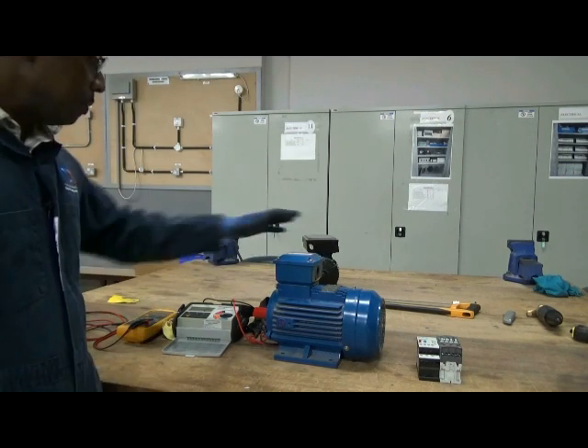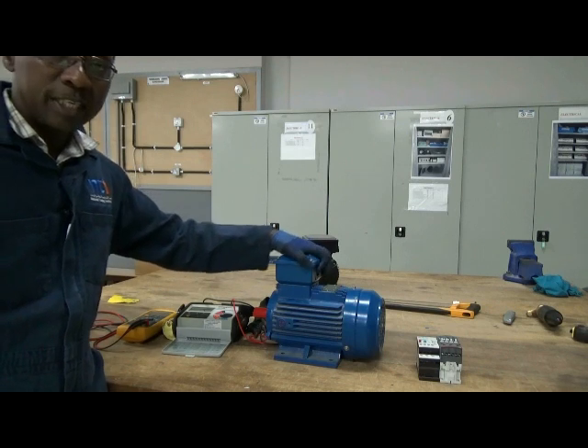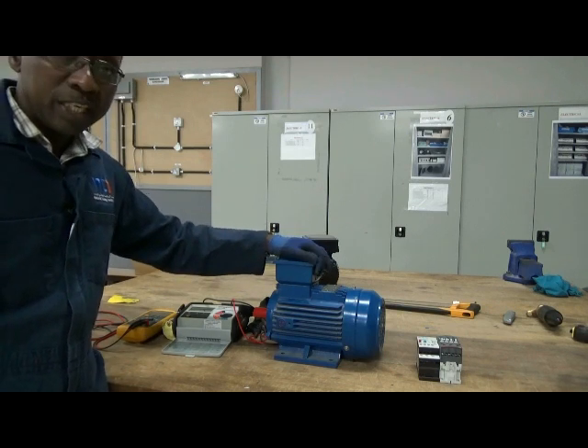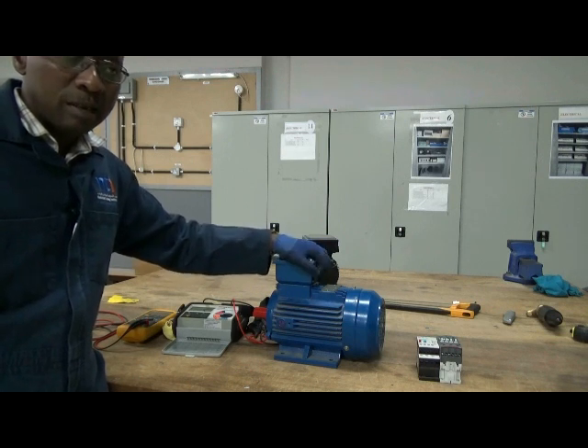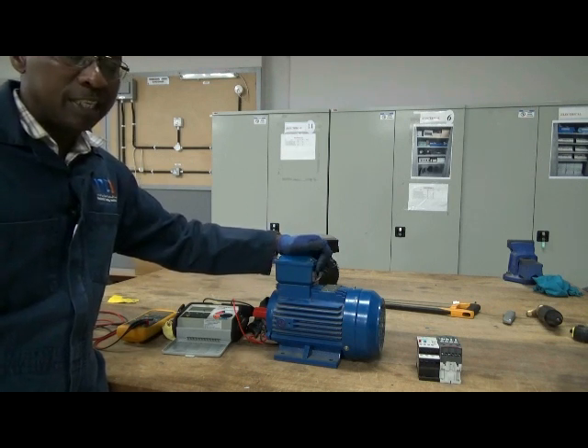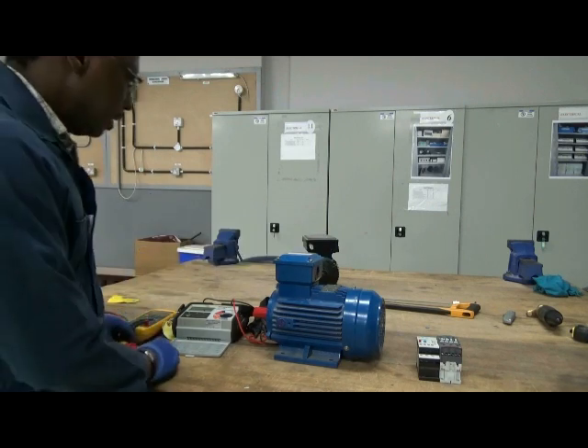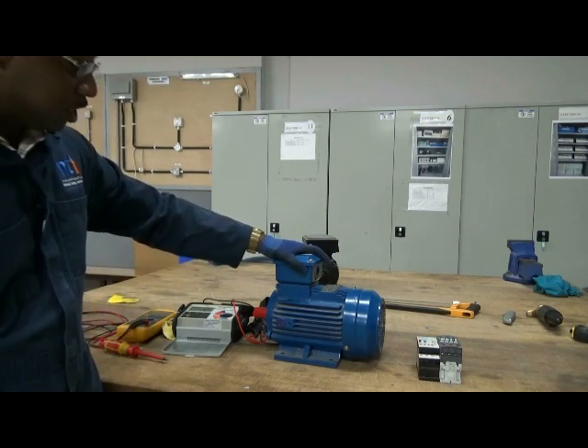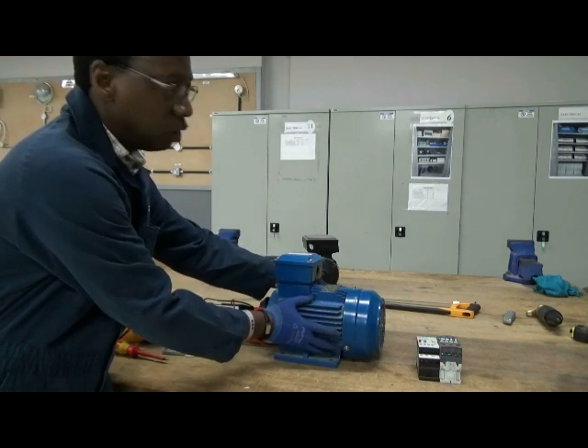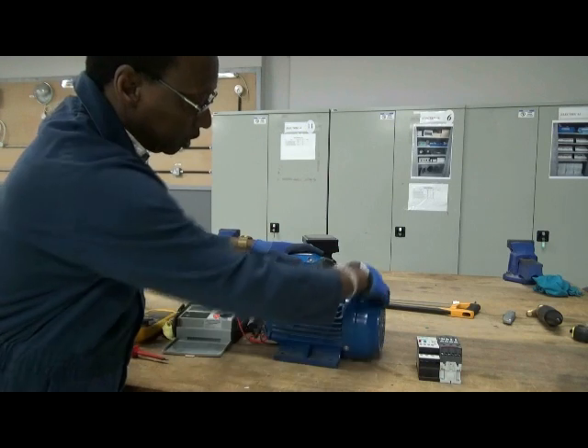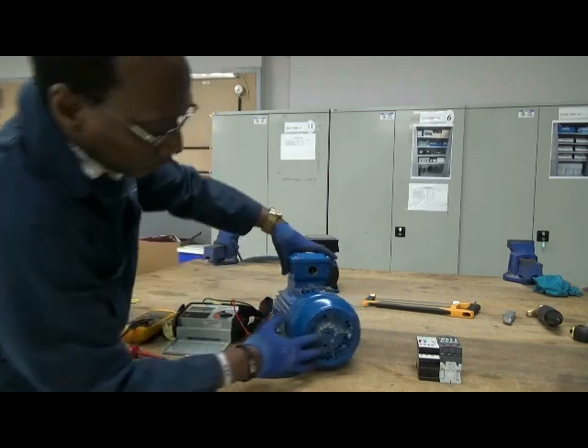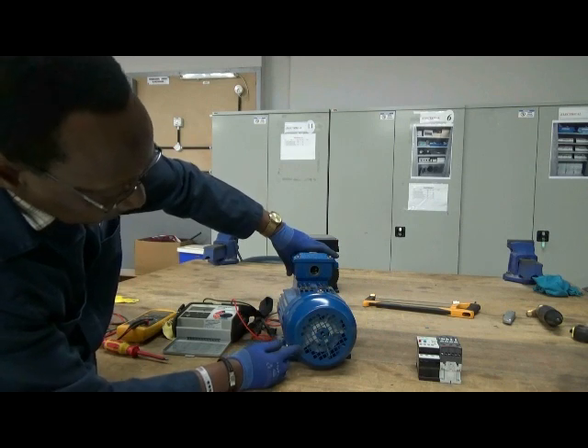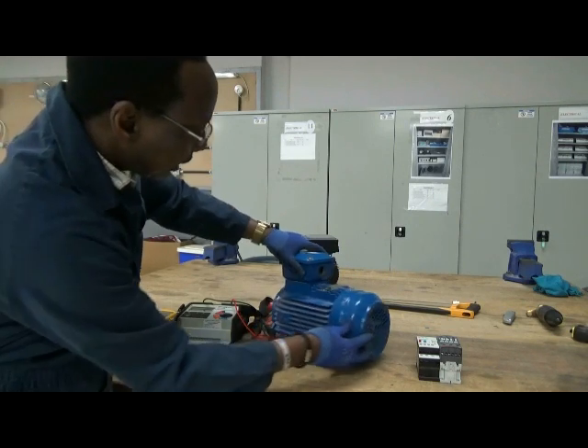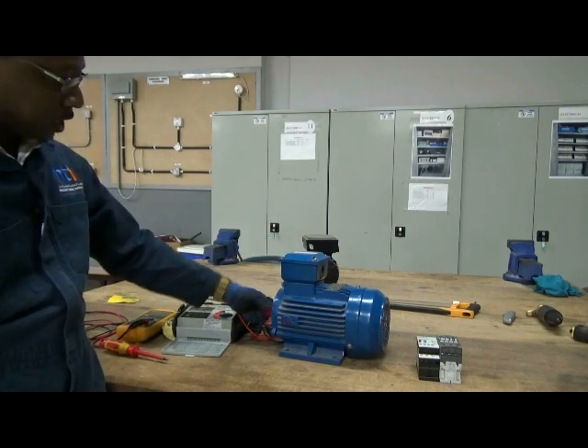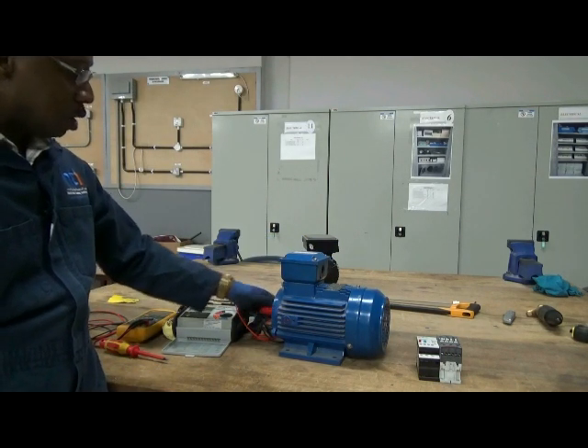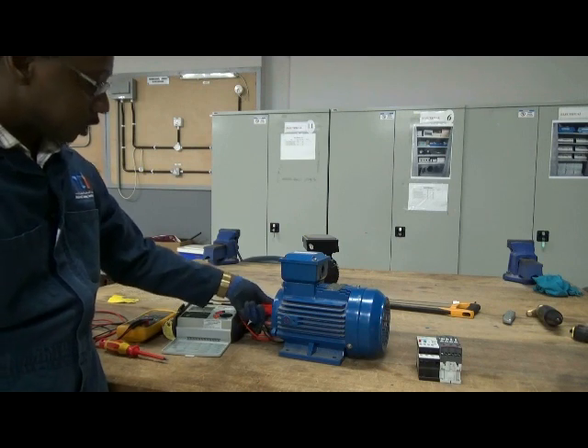Now, today, my main objective is to try and introduce to you how you can quickly determine whether the motor is functioning properly or it has been damaged. The main parts of an electric motor, as you can see, is what we call the stator, which is the outside body of the machine, and this is a fan cover. There's a small fan inside, that white thing you can see inside, that's a fan, and there's the rotating part of the machine, which is called the rotor or armature. This is the part which rotates.